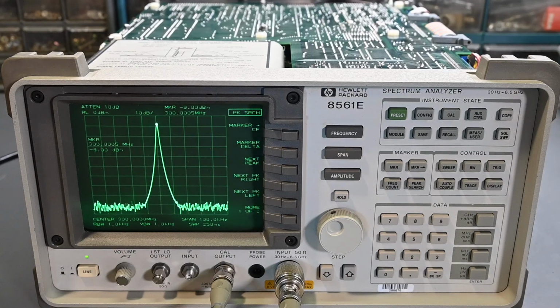So let me get this connected over to my Rohde & Schwarz signal generator, and actually before that, on the Rohde & Schwarz, we need to make sure that the output signal is exactly, we'll go with a minus 10 dBm signal and then make the calibration adjustment on the reference line. So for that, I need to connect it over to my power meter, and we'll take a look at that next. So let me do that.